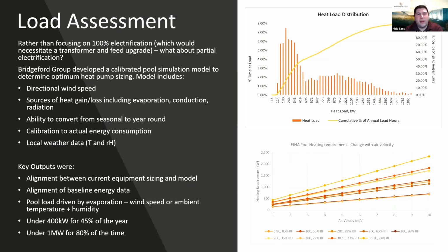We developed a calibrated pool simulation model to determine the optimized heat pump sizing and provide the financial benefits of electrifying. This model included directional wind speed, sources of heat gain or loss including evaporation, conduction, radiation, the ability to convert from seasonal to year-round, and was calibrated against actual energy consumption as well as local weather data, temperature, and relative humidity.